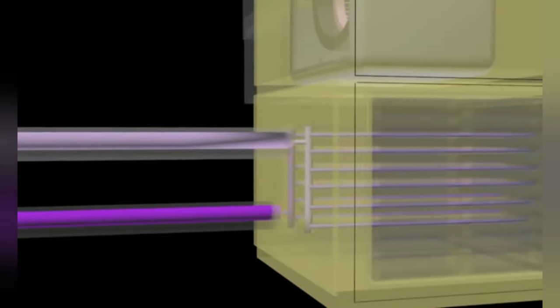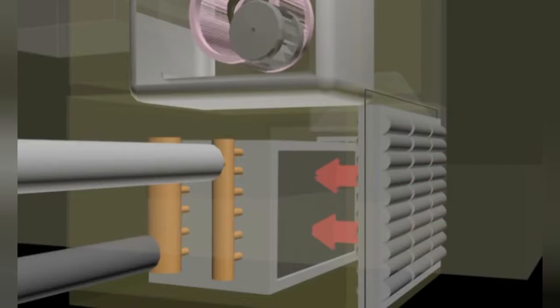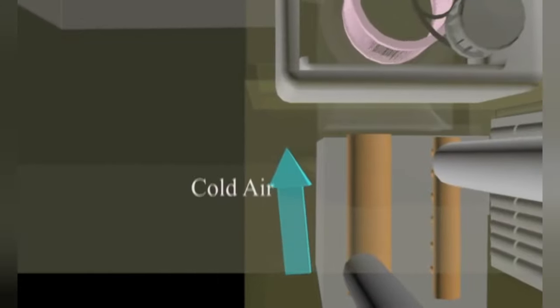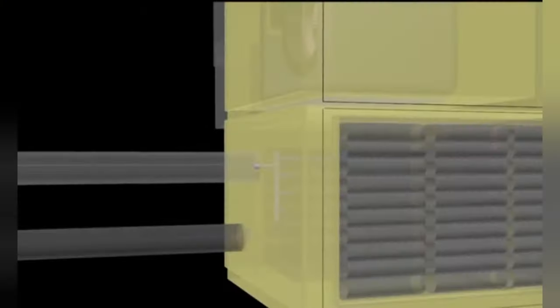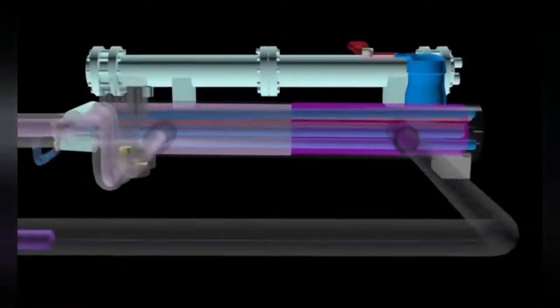In the air handling unit, chilled water passes through the cooling coil. Hot air passes over the cooling coil and is converted to cold air as heat transfers to the chilled water. The cooling coil commonly used is the tube and fin type. After absorbing heat, the chilled water is known as chilled water return, carried by a light blue colored pipe back to the chiller to transfer heat to the refrigerant in the evaporator.